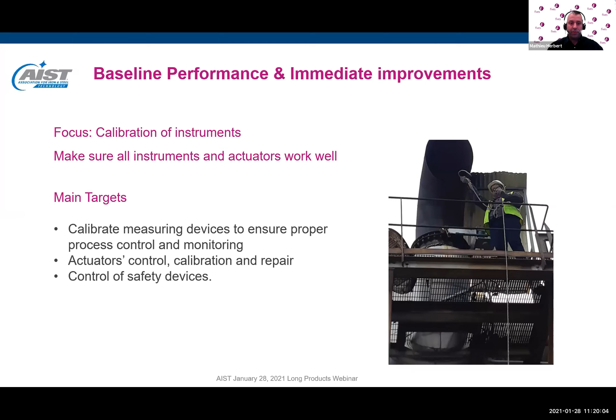A few other examples were on the list. We have the recuperator for burners running with hot combustion air. Through my history seeing furnaces everywhere, I have seen many recuperators that had issues. Sometimes they are dirty, sometimes they are leaking, and this can have a significant impact on furnace yield and fuel consumption in particular.